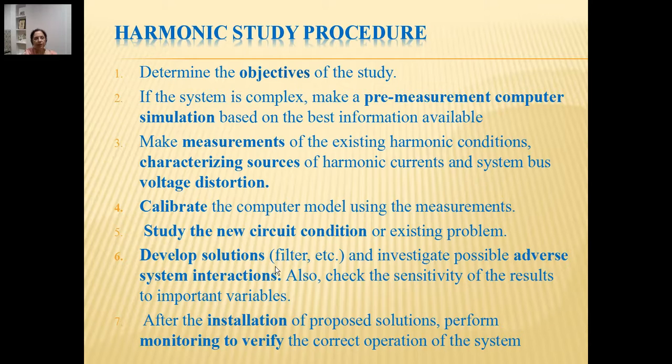What are the impacts and effects seen with different solutions? Investigate possible adverse system interactions. For example, if we connect a capacitor as a filter, it should not attract more harmonic currents and it should not form a resonant condition with the system reactance. Such adverse system interactions must also be checked beforehand. Check the sensitivity of the results to important variables. When we are trying to give a solution, it should not add to the problem, and all these conditions can be checked in simulation.